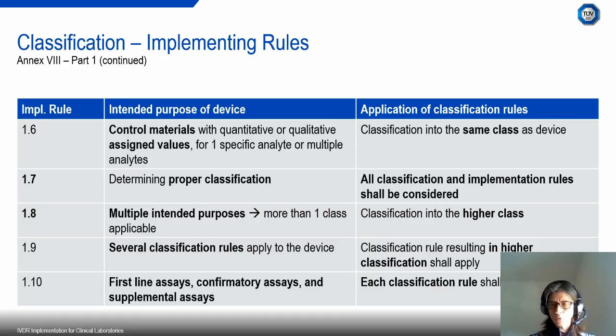I'm not sure I fully understand the question. For now, you can continue as you are. If you would like to continue using the in-house developed kit after May 2022, you would need to ensure you fulfill the requirements of Annex 1 of the IVDR, and also that you can justify why you would like to use an in-house kit versus a CE marked kit. For example, it could be that you're treating a special set of patients for which there is no equivalent CE marked kit, but you will need to fulfill the requirements of Annex 1 and have a justification as to why you cannot use a CE marked kit or device.